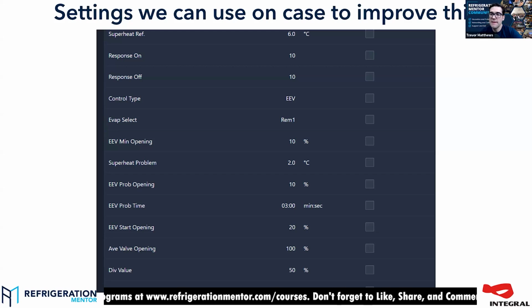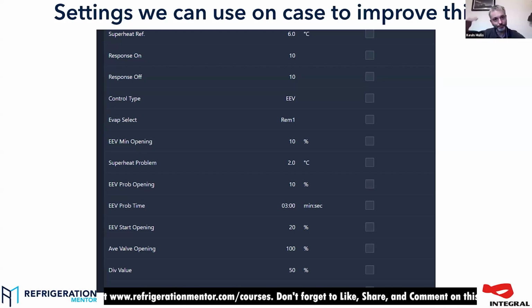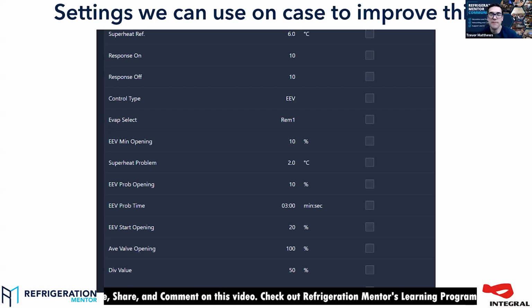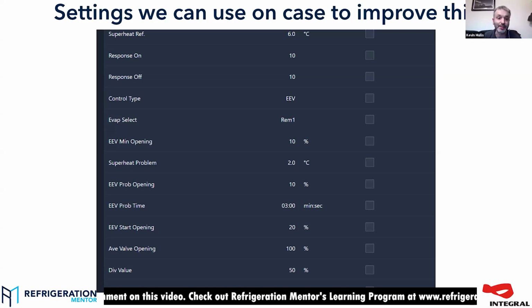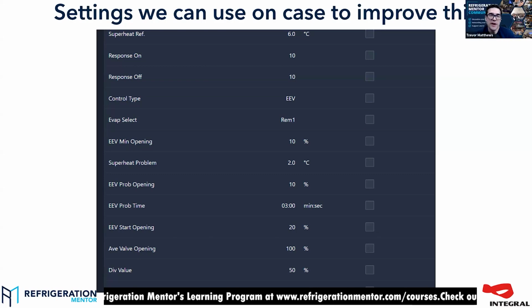Yeah. And you try and keep the liquid valve open all the time and regulate suction pressure. Certainly in the UK and I think in Europe, that setup hardly ever exists in retail, and we just cycle the temperature based on using the liquid valve. There are no EPRs because most of the systems are installing ring mains. So it's a different challenge because, and to be honest, I think we're missing a trick this side of the pond with it, because actually the EPR-based system is likely to be inherently a lot more stable if you get it right. That is for HFC systems.